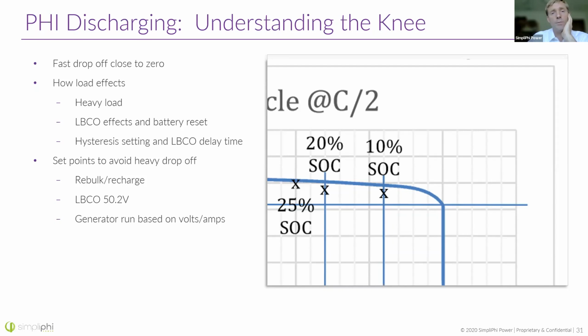And so if you're sneaking up on it, if you're discharging very slowly, then the battery management system will likely catch that, and you won't have the battery management system trip. Sometimes if a battery is run all the way down very slowly, the system will catch it. But if you do it really quickly, sometimes the battery will need to be reset. And the way you do that is you just flip the breaker off and on the battery.